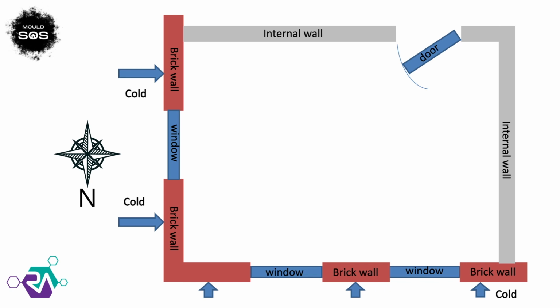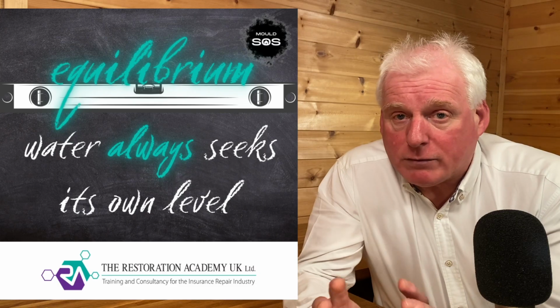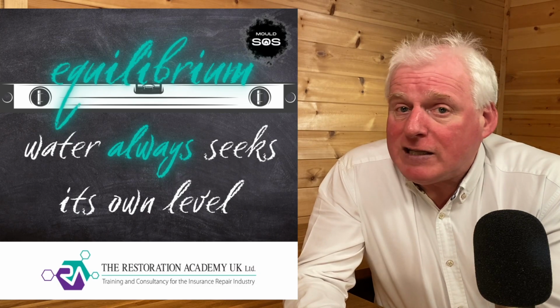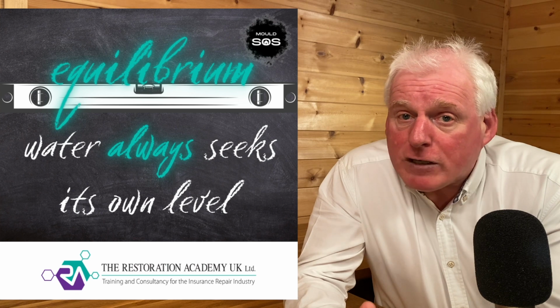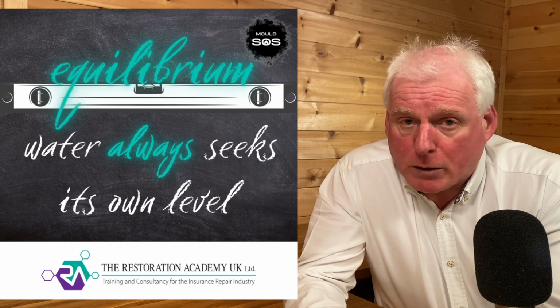Let's take a reading of the indoor conditions. If the readings are 60% relative humidity and 20 degrees centigrade, then the humidity ratio is 8.8 grams of water per kilogram of air. Because water seeks its own level, equilibrium, whether a solid, liquid or a gas, that will be evenly distributed across the whole room in normal circumstances.